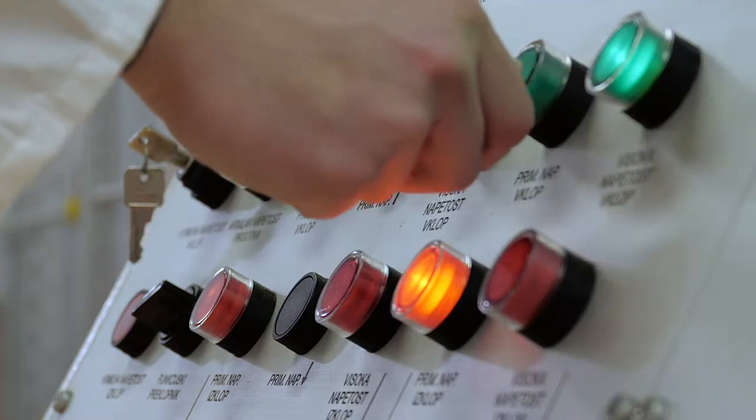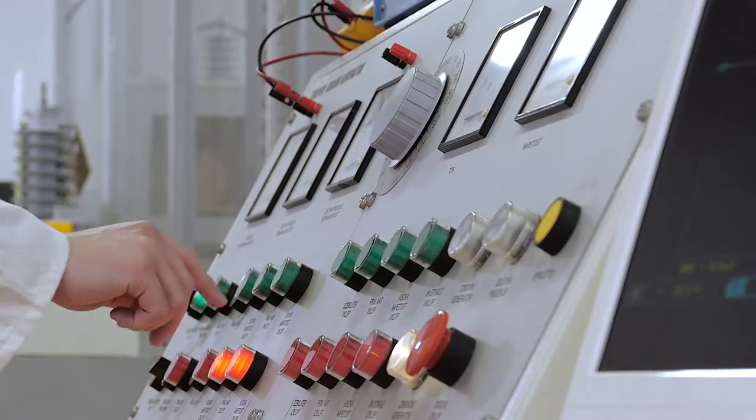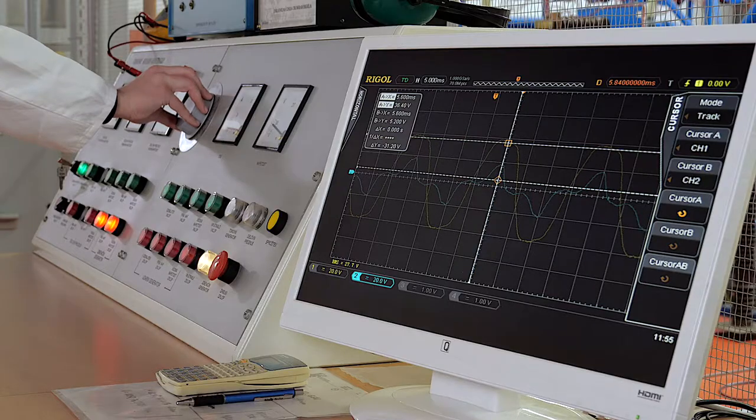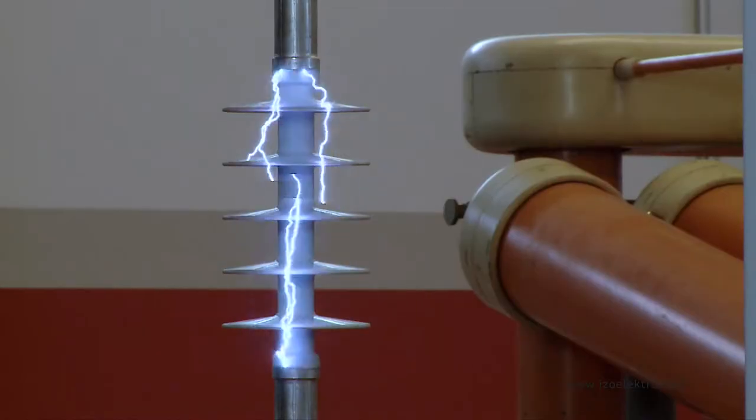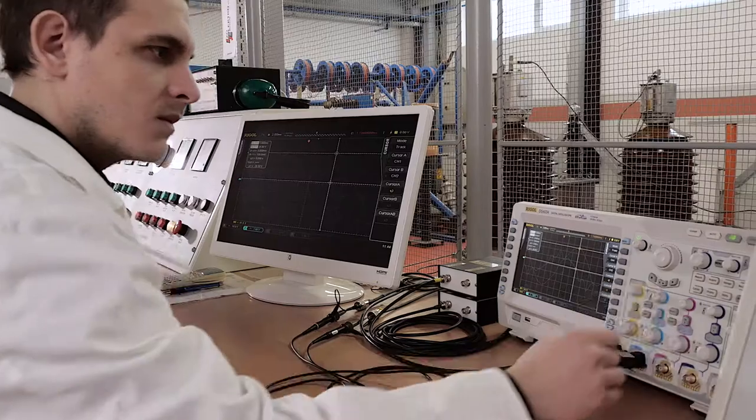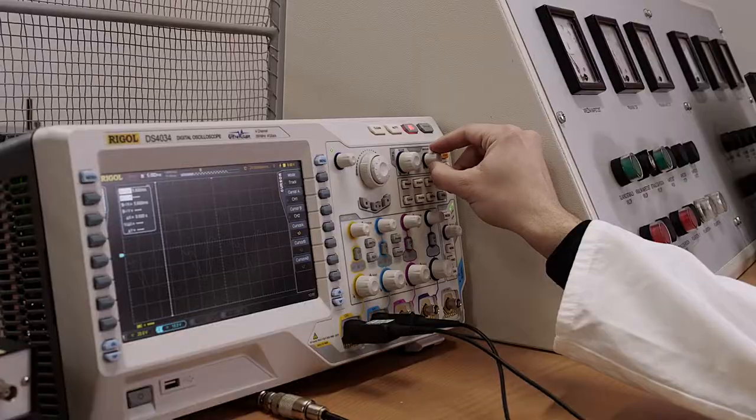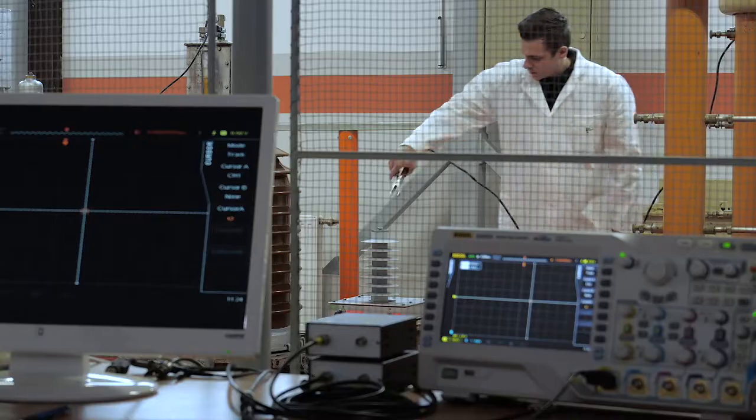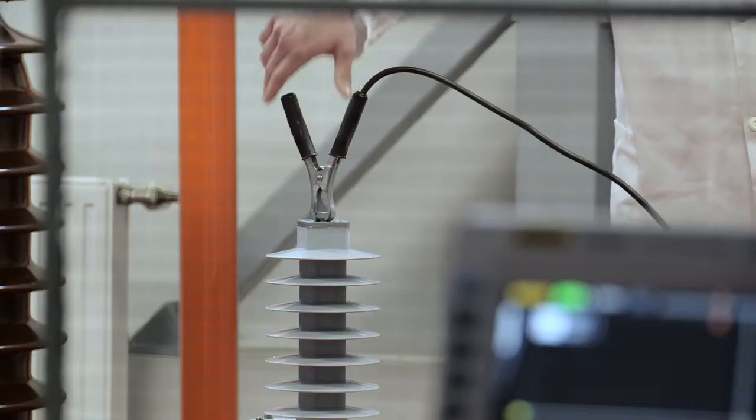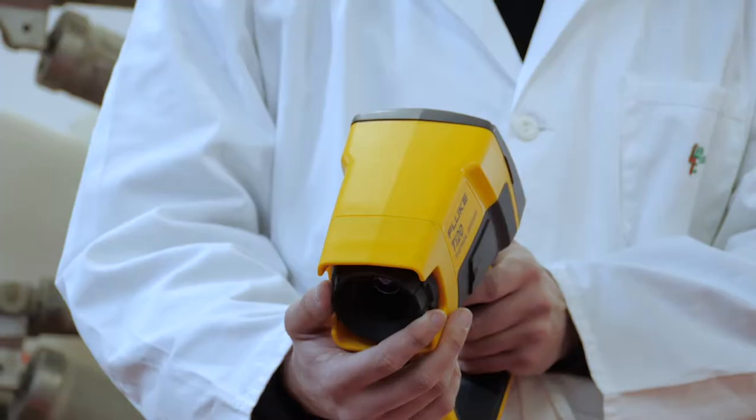We have our own high voltage laboratory that enables us to run tests with alternating voltages of up to 220,000 volts and 1.2/50 microseconds wave shaped lightning impulse voltages on medium voltage surge arrestors up to 50,000 amps. The lab allows us to run most standard tests on medium voltage surge arrestors.